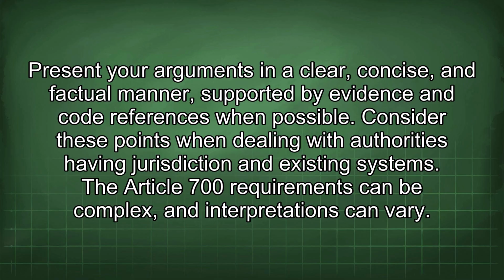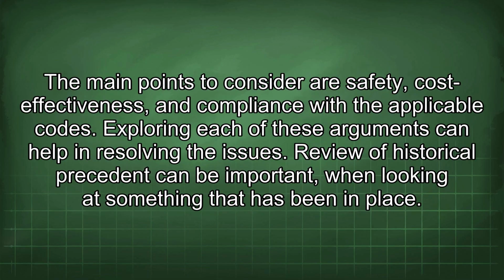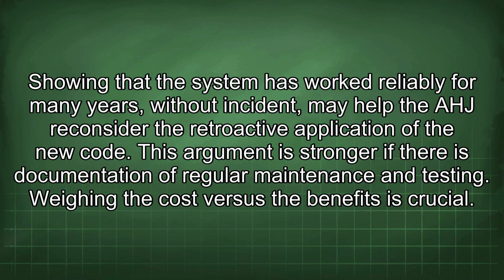The Article 700 requirements can be complex and interpretations can vary. The main points to consider are safety, cost-effectiveness, and compliance with the applicable codes. Exploring each of these arguments can help in resolving the issues. Review of historical precedent can be important when looking at something that has been in place. Showing that the system has worked reliably for many years without incident may help the AHJ reconsider the retroactive application of the new code. This argument is stronger if there is documentation of regular maintenance and testing.